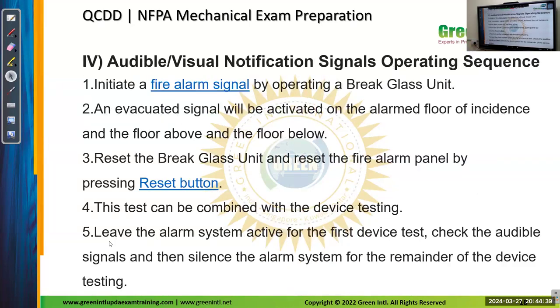Audible visual notification signals operation sequence. First we will initiate the alarm signals by operating the break glass unit. An evacuation signal will be activated on the alarmed floor of incident and the floors above and below. Reset the break glass unit and reset the fire alarm panel by pressing the reset button. This test can be combined with the device testing. Leave the fire alarm activated for the first device test, check the audible signals, and then silence the alarm for the remainder of the device testing.